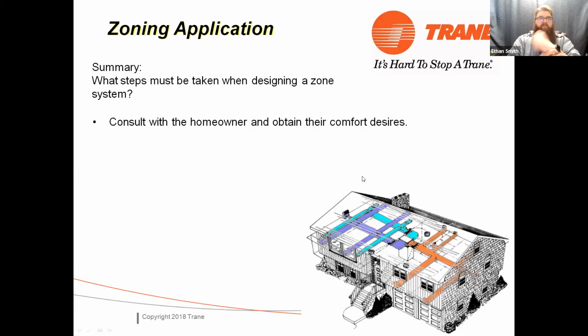Okay, so we got to play on the worksheet here. Number one, guys, when we're designing zoning systems, you got to talk to the homeowner. Make sure that they understand what they're going to get. Make sure that their expectations are realistic. Sometimes you got to take that homeowner down a notch or two. They want that 8x8 laundry room on its own zone. They need to understand what that's going to do, what you're going to have to do to accommodate that.